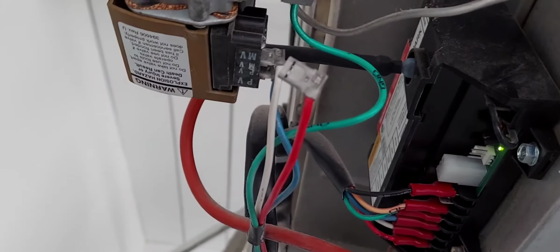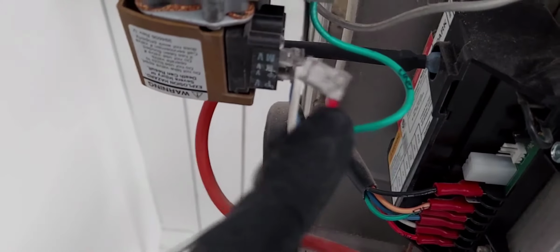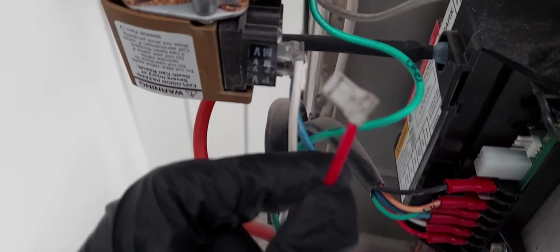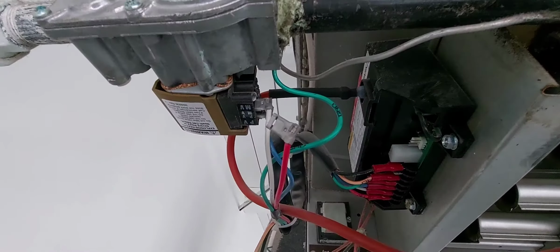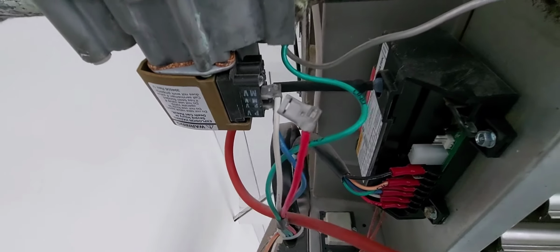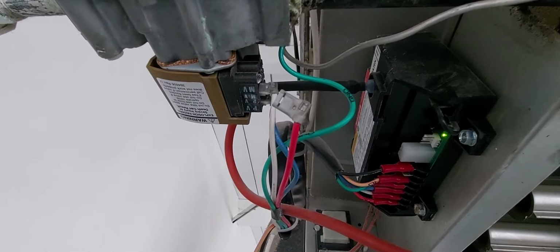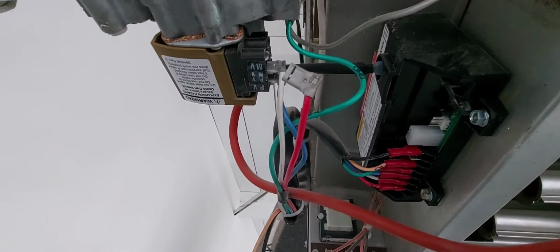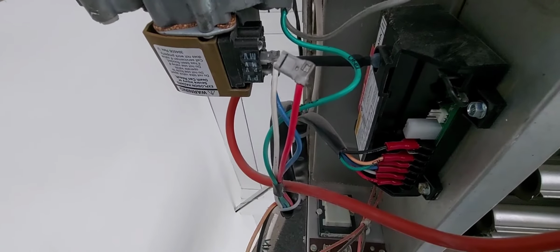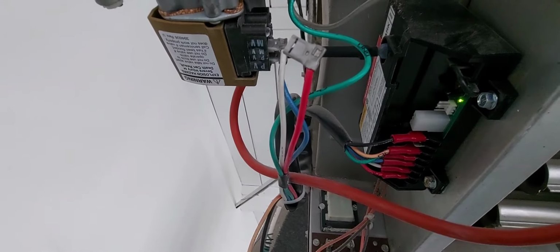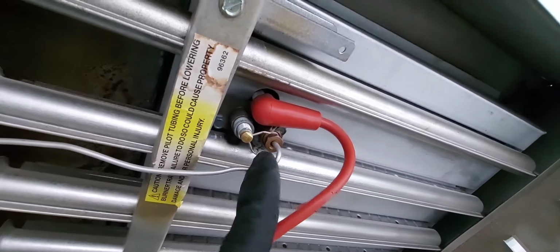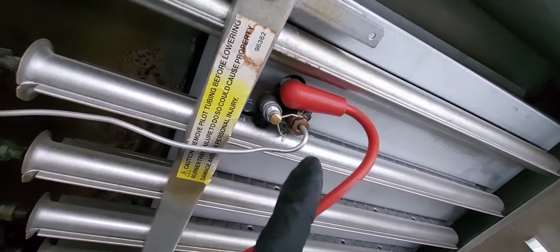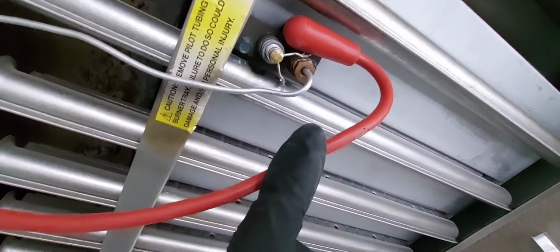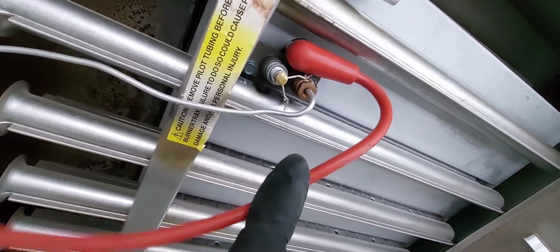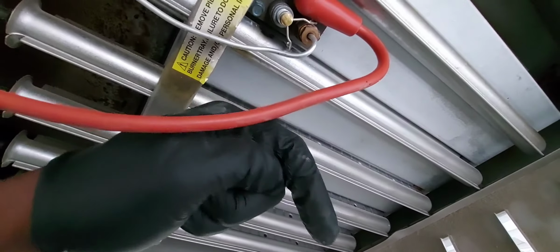So I went ahead and disconnected the MV from the gas valve. Okay, and that's basically the main solenoid in the gas valve. So the reason why I do that is that I'm going to uninstall this right here, the pilot assembly, and I have a video on replacing the pilot assembly, and I'll leave the link in the description.